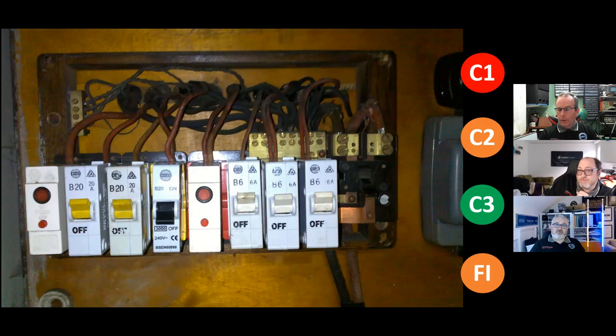And that's the trouble. The minute I touch it, I could be deemed as altering it, and I don't want that. So for me, it's a C2 with an FI. I could offer, look, I'll visually check sockets and lights for direct access, but it would still be an unsatisfactory. I could walk around and say, look, your lights work, your switches are all good, there's no cracks, no signs of thermal damage, but your board, the wiring is 60, 70 years old, there's signs of degradation on the cabling, your insulation values are low, you haven't got equipotential bonding, it's a failure. I recommend a full bonding scheme, a rewire and a new consumer unit.